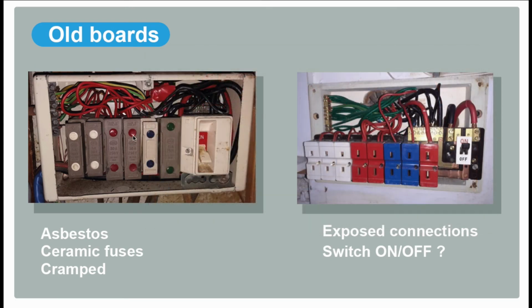The ceramic fuses as well, they can crack and break. These little dots, these can pop out and there's live connections behind them. It's also a little bit cramped to work in as well. I know we're stripping it out, but no, don't use this. If you've got a fuse board like this, there's a procedure we're going to go through. What you do when you've got an asbestos fuse board, you don't want to start pulling the fuses out.